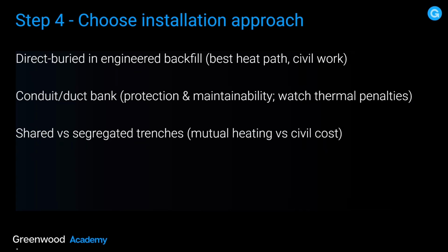Direct buried in engineered backfill, best heat path, civil work. Maybe use a conduit and duct bank, protection and maintainability, watch for thermal penalties. Take into consideration shared versus segregated trenches, mutual heating versus the civil cost. Like all things on all projects, it really comes down to a cost-benefit analysis. For example, using an engineered backfill may seem expensive, but maybe it's the least expensive of any other option.